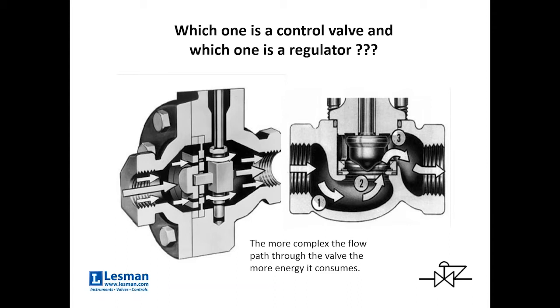Is there a relationship between energy consumption and pressure drop across that valve? Absolutely. The more complex the flow path, the more energy that valve will drop in a given size. You can change the size of the valve from bigger to smaller, and you can also change the complexity of the flow path. The complexity of the flow path can also be your friend. The more complex the flow path, the less likely it is to cause trouble in the form of noise, flashing, or cavitation.